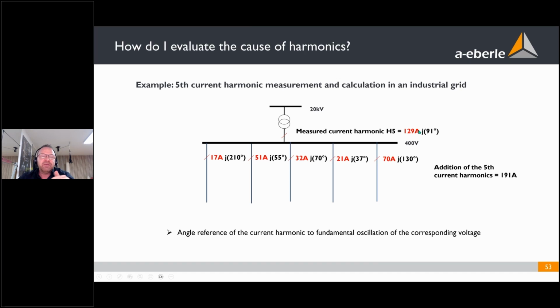So we, even the old PQ-Box 100, deliver the phase angle of the 5th harmonic compared to the fundamental of the voltage. So this is a basis. Now we can analyze that some of the producers of the harmonic, like here, are positive for the network and some are negative.